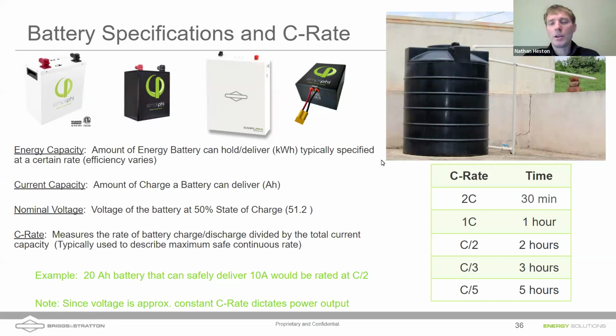If you had a 10 kilowatt hour battery running a 5 kilowatt inverter frequently, you'd be heavily taxing that battery at the C/2 rate repeatedly, and it would age faster. So the reason we don't want to go into an old, undersized battery bank and add multiple new batteries is that the degraded older batteries will do less of the work, and they'll age the newer batteries faster.